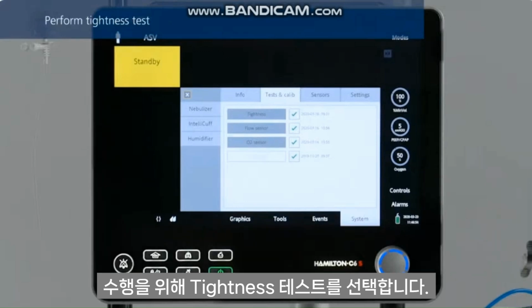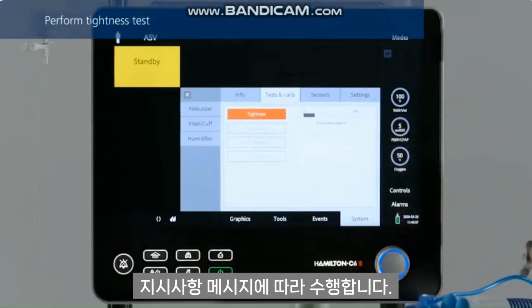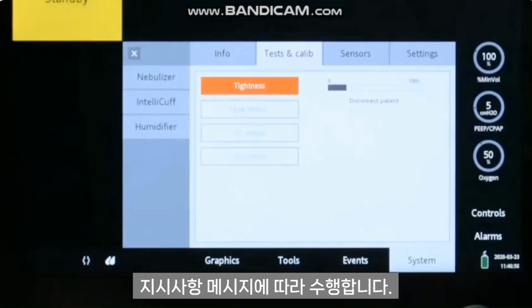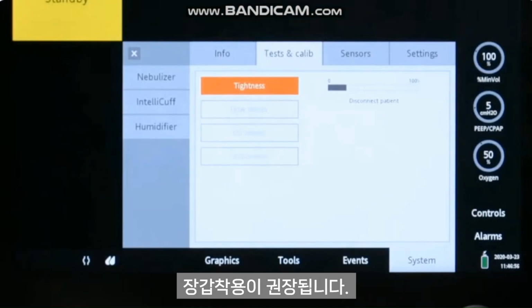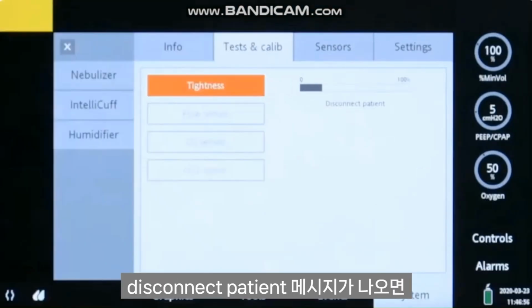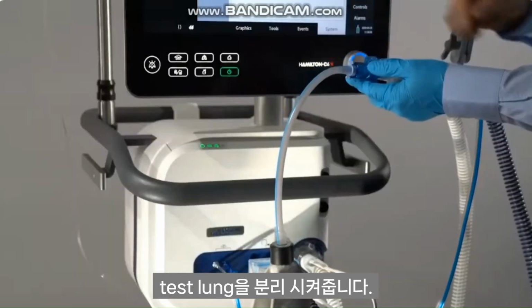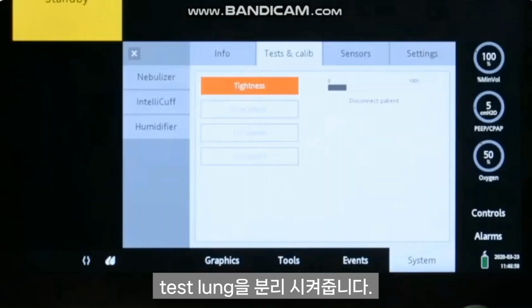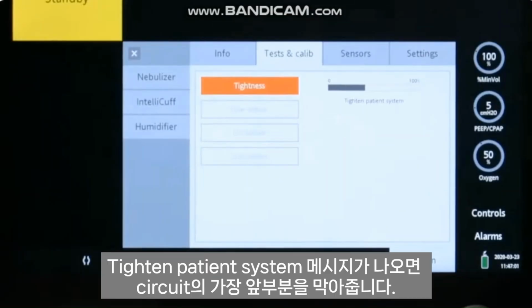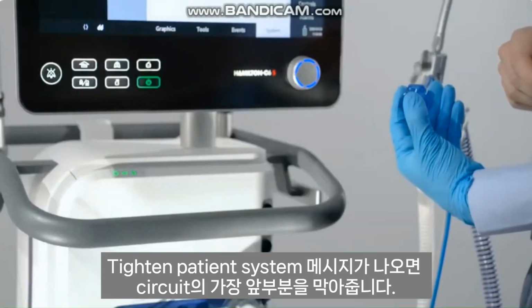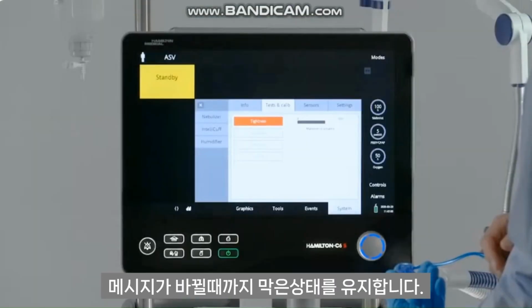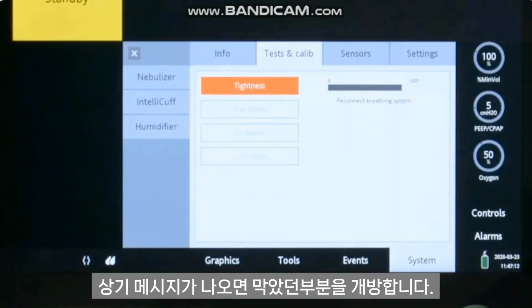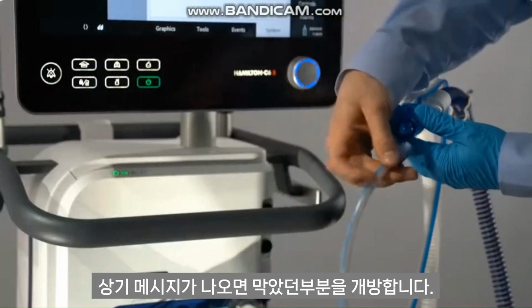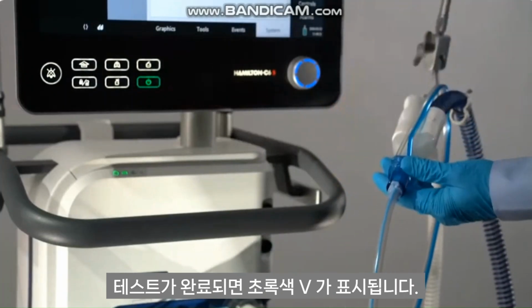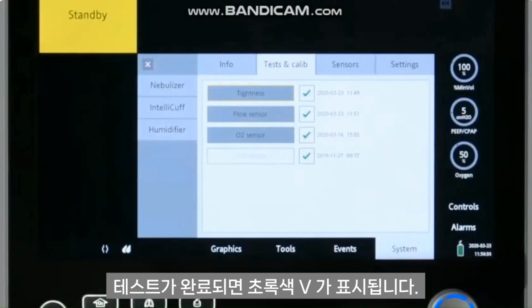To perform the tightness test, select the desired operation. Then, follow the instructions from the ventilator. Please note that wearing a glove is recommended. When the Disconnect patient message appears, disconnect the test lung. When the message Tighten patient system is displayed, block the opening. After completing the tightness test, the message Reconnect breathing system is displayed. Reconnect the breathing system. When the test has been completed successfully, a check mark will appear.